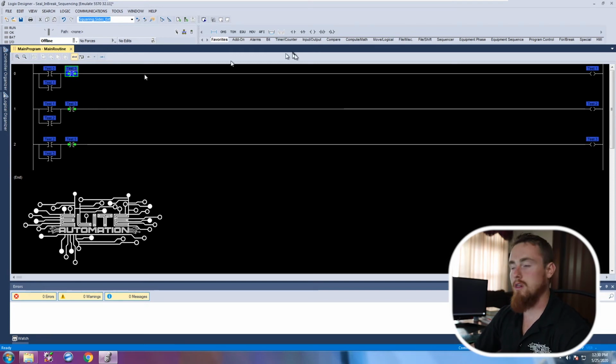This is the seal-break part of the logic. Basically, after this rung fires, it'll then fire this next rung and this coil. When this coil activates, it'll break the rung before it. And then it'll consecutively do the same thing. The reason you have this seal-in is because when this first rung breaks, this first rung is the one that's firing the second rung. So as soon as this fires and breaks the rung before it, you need something to hold this second rung continuously on. What you do is use the contact of its own coil of that same rung of logic.